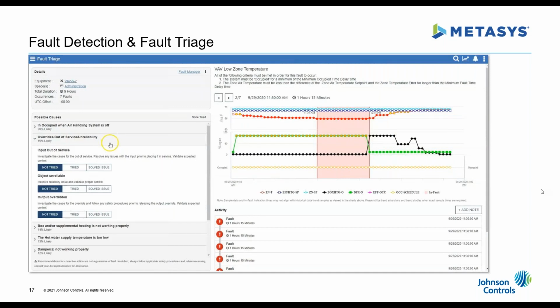So now we're getting into a portion of the fault detection called fault triage. And as I mentioned before, the fault detection and the fault triage are licensable features. So if fault triage is also something that you would like to take advantage of, we can add that to the system, and now you're going to get a knowledge base of causes for a particular fault. So again, we're looking at a VAV low zone temperature fault here. And now it is actually giving us possible causes for that fault. So a new operator, or even a seasoned operator, that is maybe not familiar with the building can really start to take action immediately without having to try to understand what's going on in the system, because you're going to get those possible causes. And this knowledge base is built on over 150 years of Johnson Controls BAS knowledge and HVAC knowledge. So this has got a huge knowledge base of information built in already.